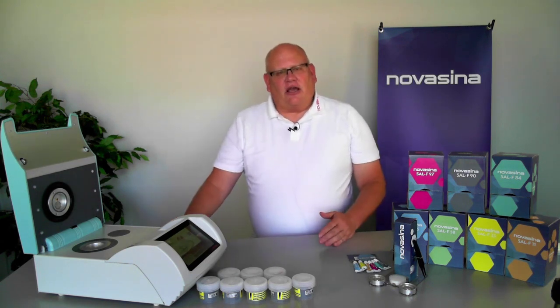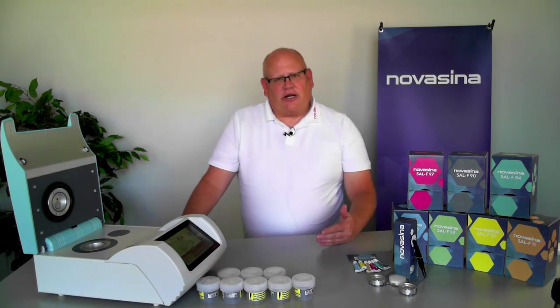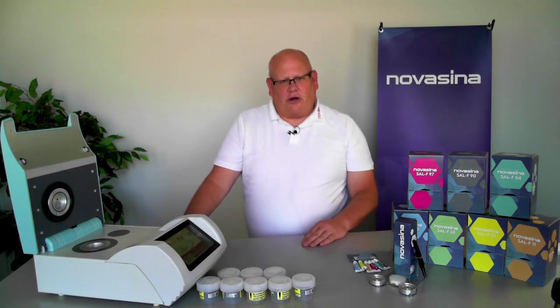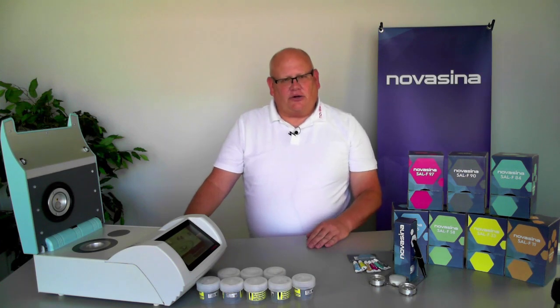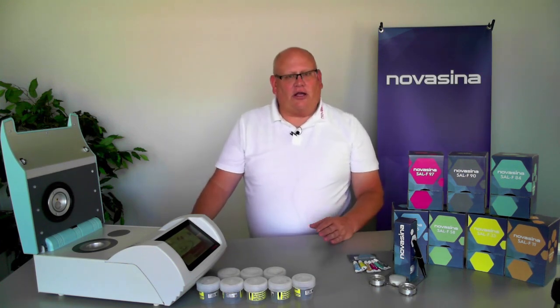The salt standards available for checking water activity instruments come in two types. One is saturated salt slurries — salts that have known water activities when they're at saturation. The other is unsaturated salt solutions, where the water activity is based on concentration. Novasina is the only water activity instrumentation company that offers both types of standards, and each has its own pros and cons.